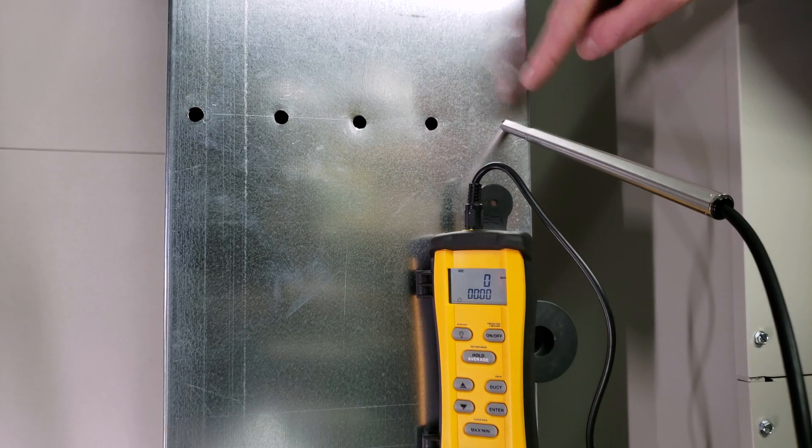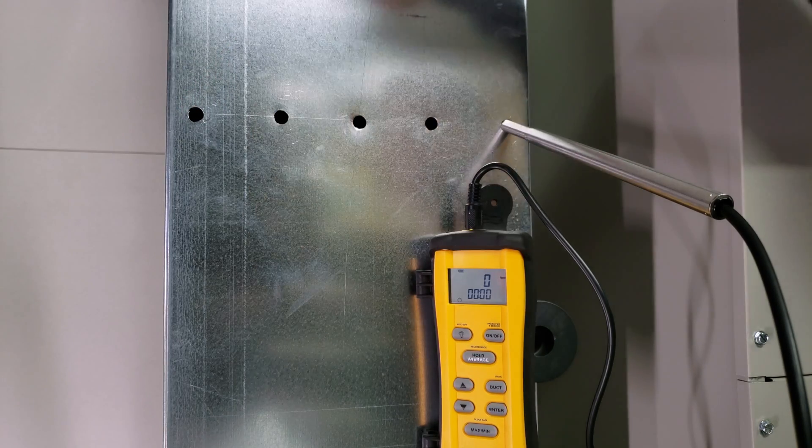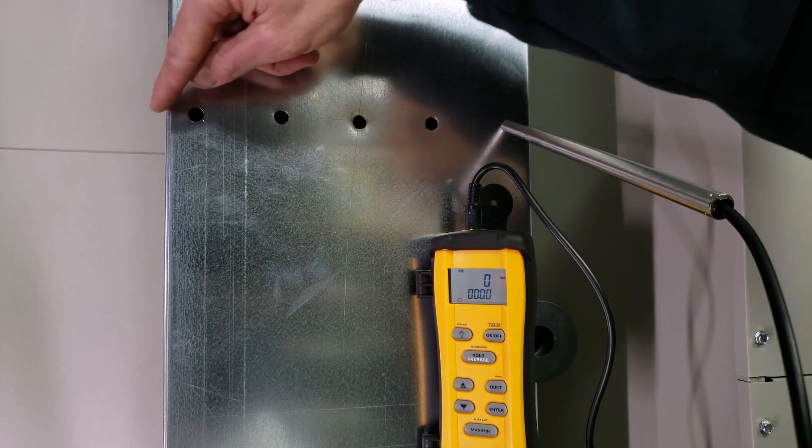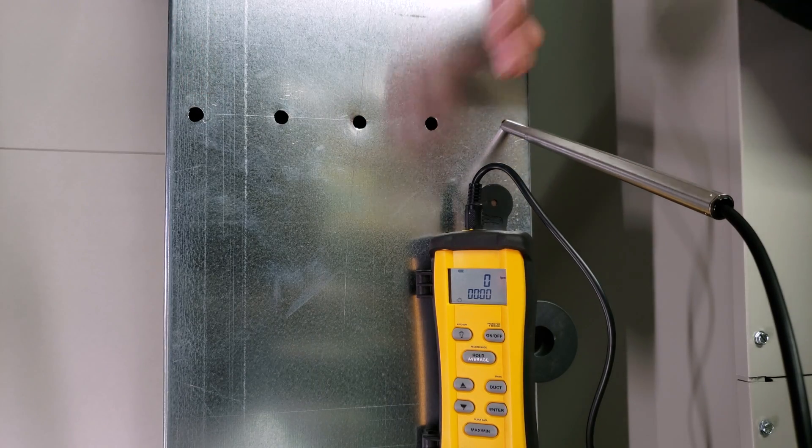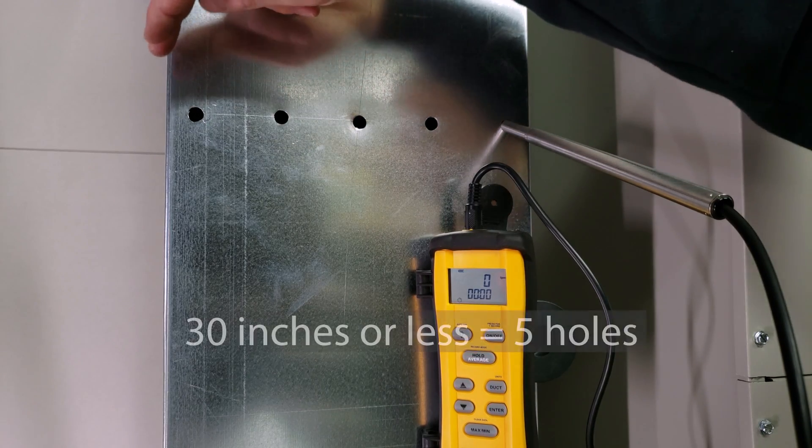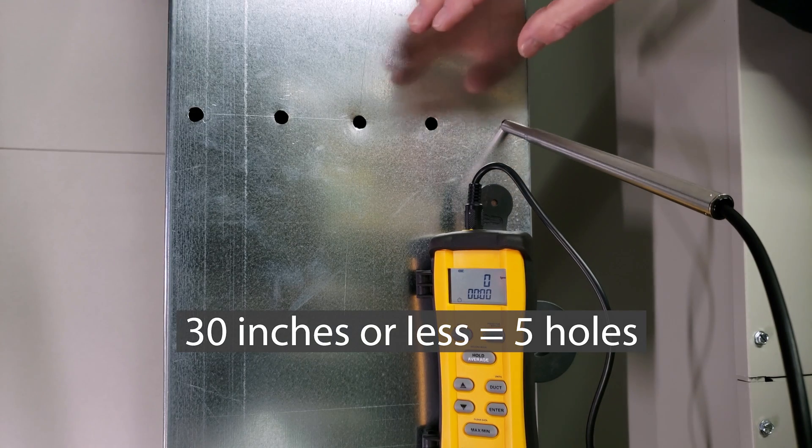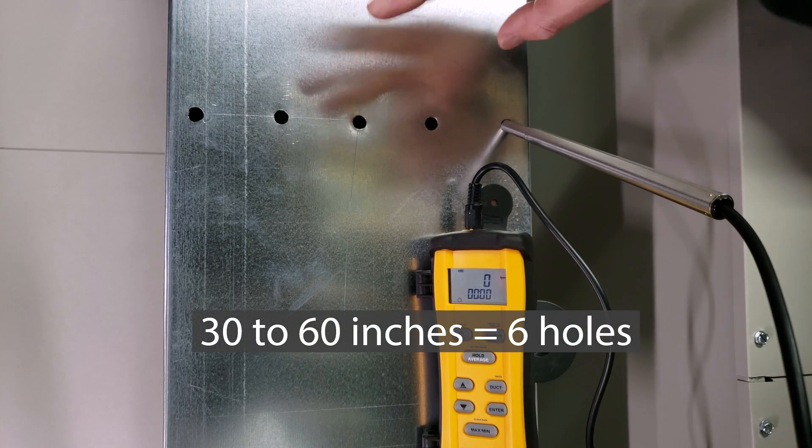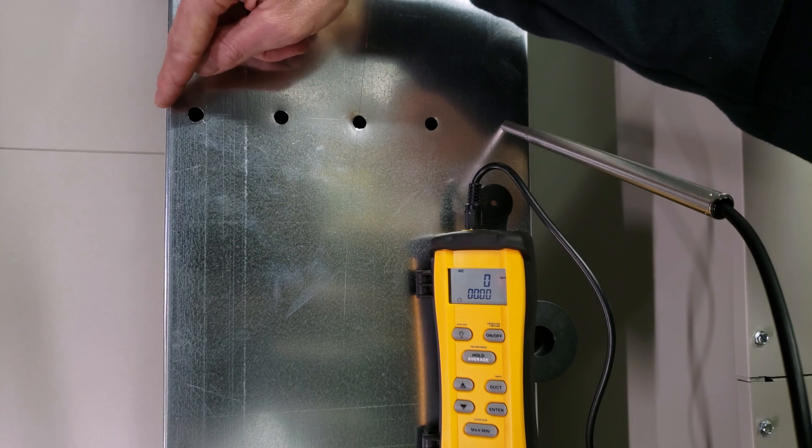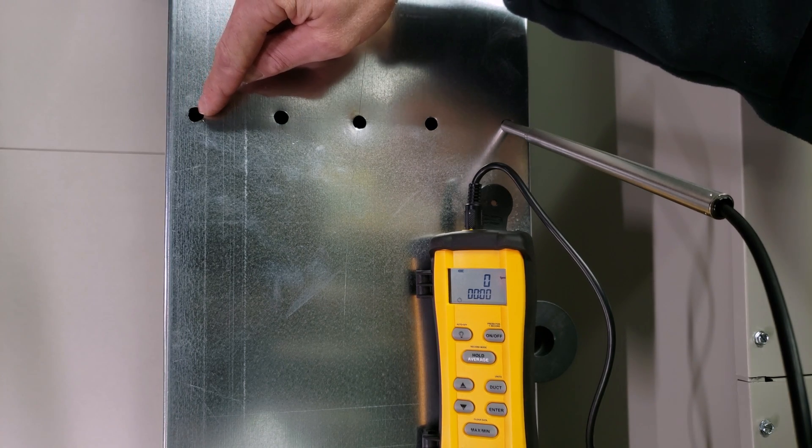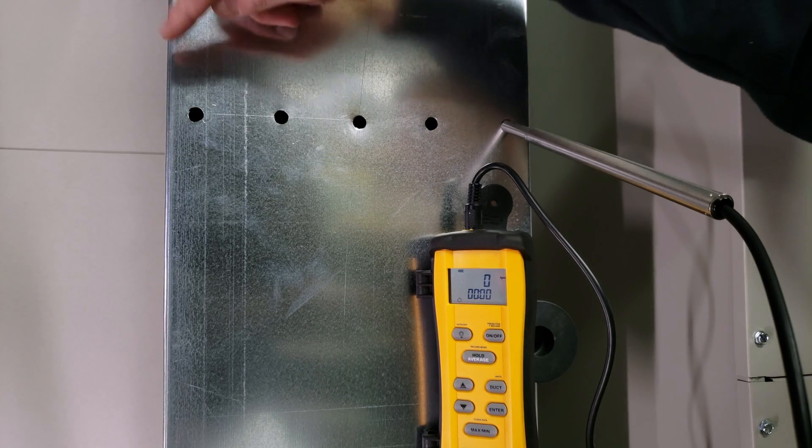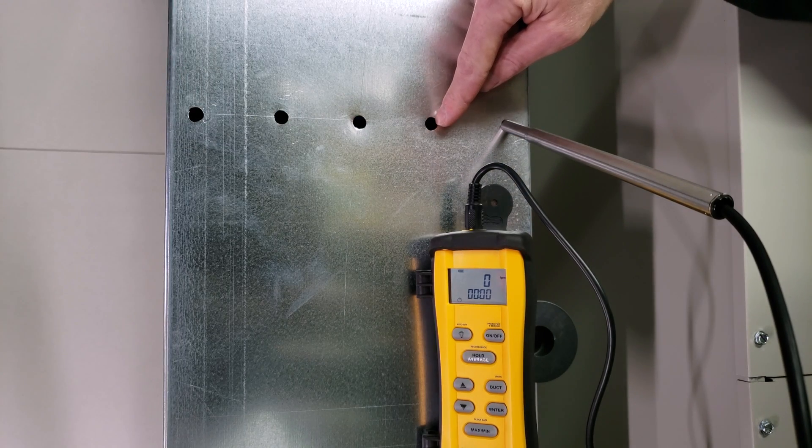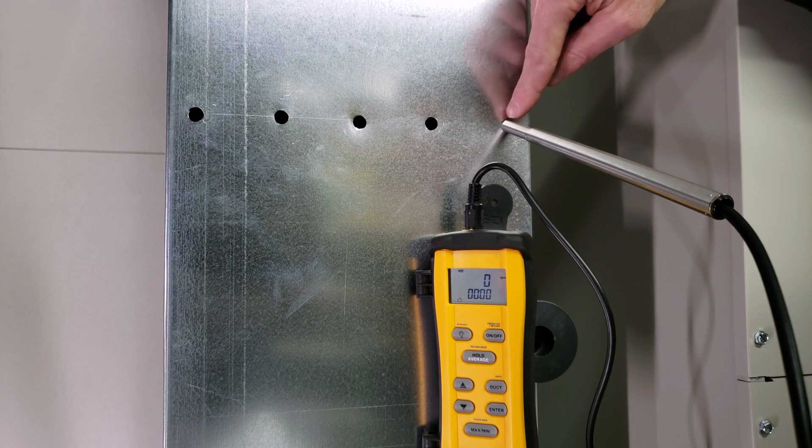We already have our holes drilled, but to determine where holes need to be drilled, ensure it's in a long straight section of duct close to the air handler. If the duct is less than 30 inches, drill five holes. If between 30 and 60 inches, you'd need six holes. For five holes, traversing points are at 7.4%, 28.8%, 50%, 71.2%, and 92.6% of the duct width.